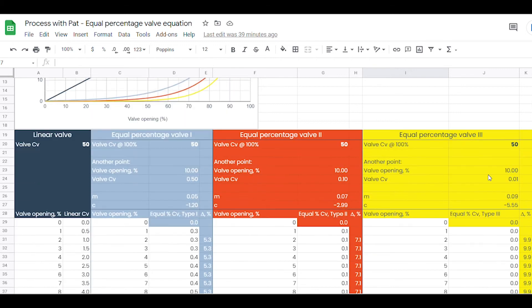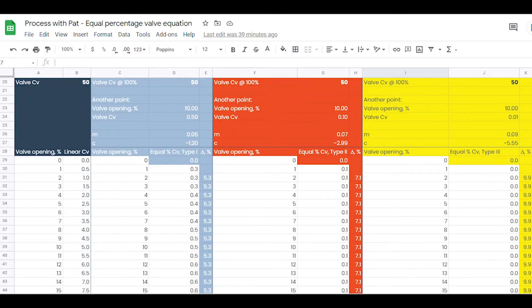The first valve has a constant 5.3% increase in flow for every additional percent valve opening. The second valve increases flow by 7.1% for every additional percent valve opening.